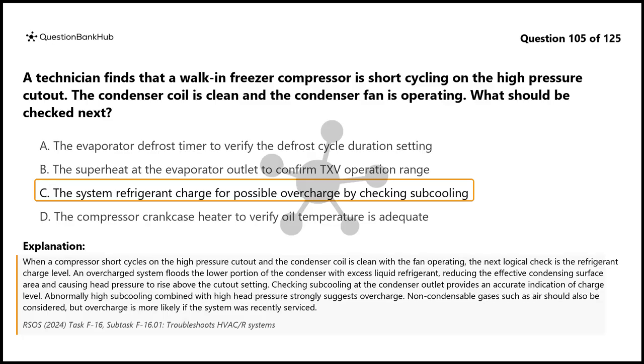Checking subcooling at the condenser outlet provides an accurate indication of charge level. Abnormally high subcooling combined with high head pressure strongly suggests overcharge. Non-condensable gases such as air should also be considered, but overcharge is more likely if the system was recently serviced.